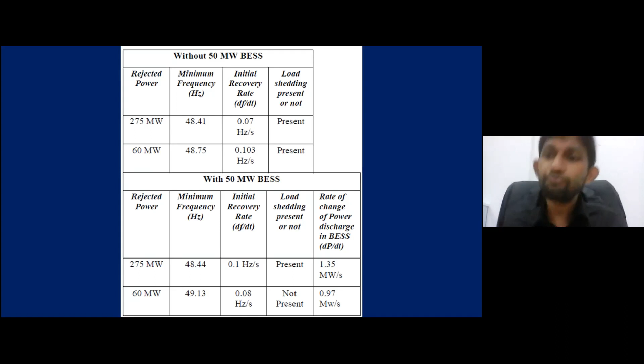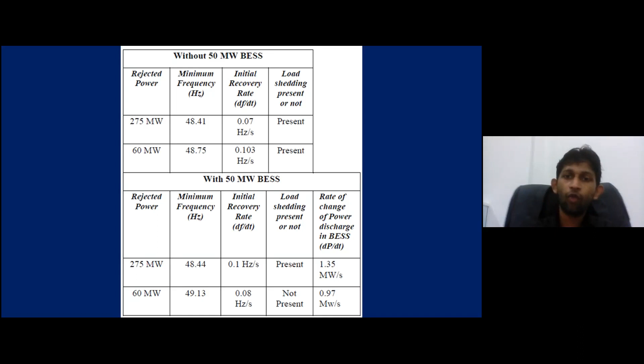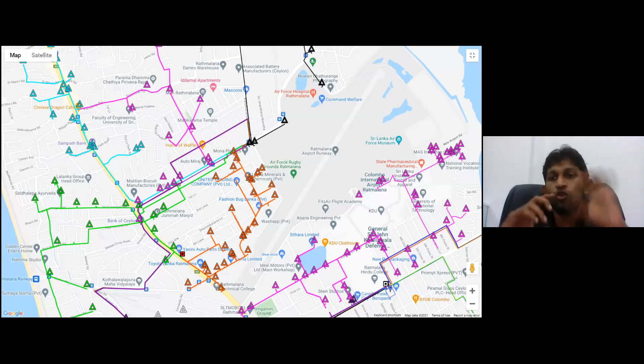Now, afterwards, what I did was we isolated a feeder, and I wanted to see whether we can achieve a smooth transition from a battery energy storage system to cater the power for that particular feeder until load shedding is completed and the system is restored. For this I chose the 7th feeder of the Ratmalana grid substation. Here you can see the red circle is the Ratmalana grid, and the gray circle is a primary substation. So we have 33 kV feeders going up, and then we have the primary substation.